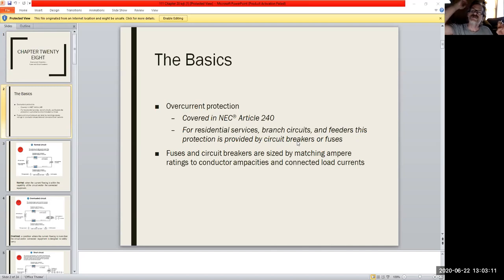So the very basic ones that they first came up with were fuses in different styles, but generally it's like a metal filament with a certain width, and that's basically designed to handle the currents up to what it's rated for. Anything over and above that for a given time period would eventually burn through that filament and disengage.